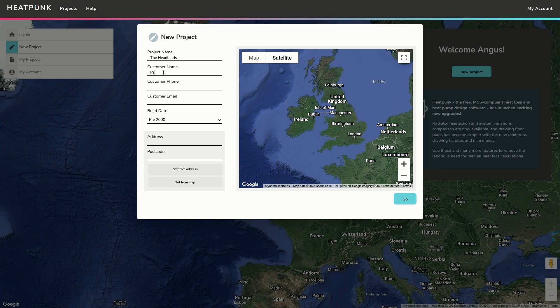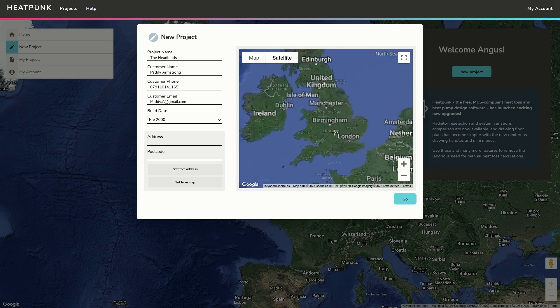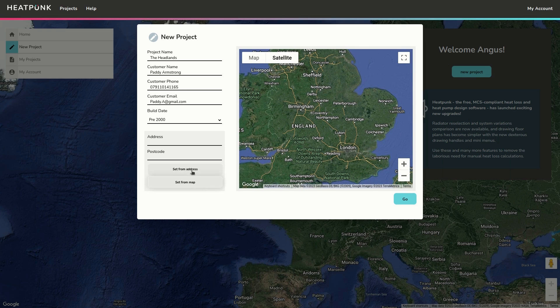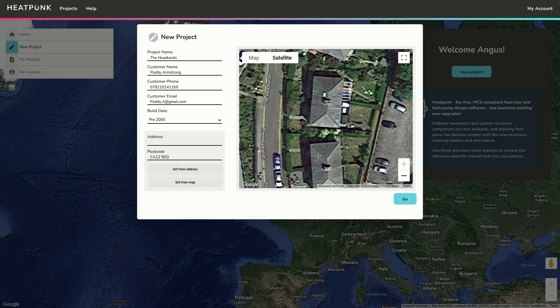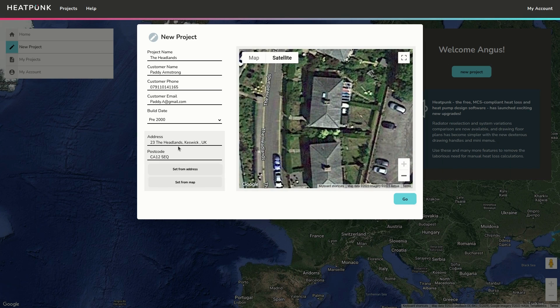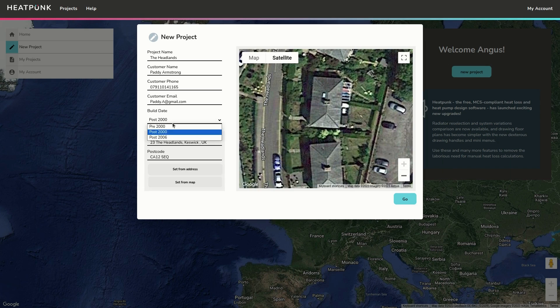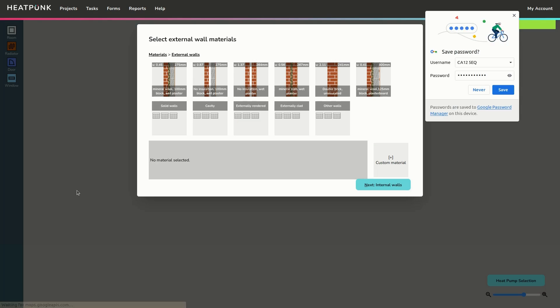As well as the address of the property — there are a couple of ways to do the address. Either you can zoom in and locate a property and set the address on the map, or you can enter a postcode and then set from address. You can find the correct property, click 'Set from map' and it will populate the address. There is also a build date dropdown to choose between pre-2000, post-2000, and post-2006, which will determine the ventilation rates and air changes for the rooms based on the Domestic Heating Design Guide.